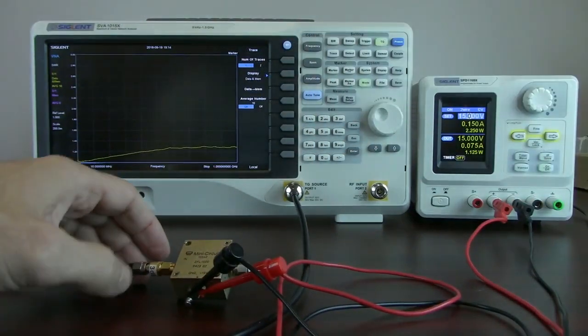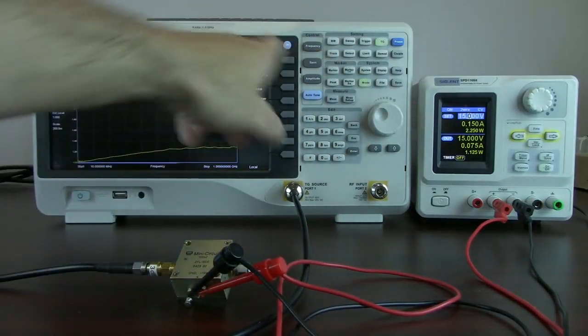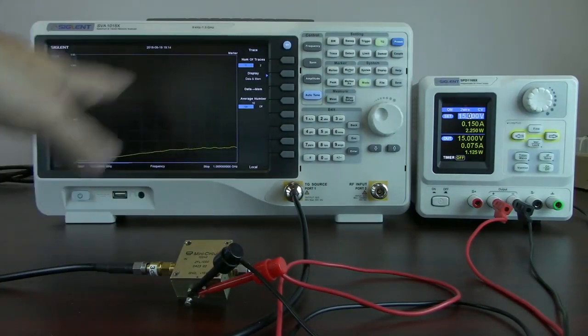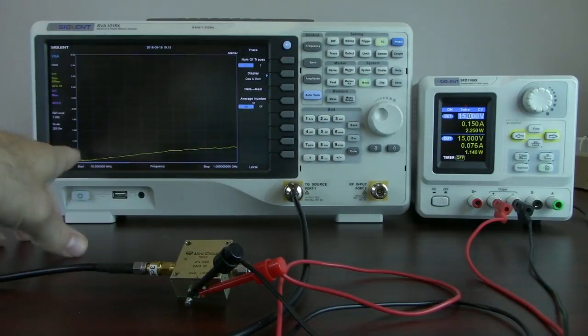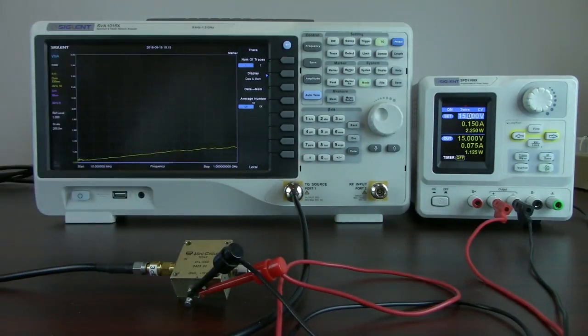By selecting trace, I can now pull in different trace values and show different traces on the display. I set the average number to 10, and so you can see we've got a nice curve here that's very close to what we see on the datasheet.